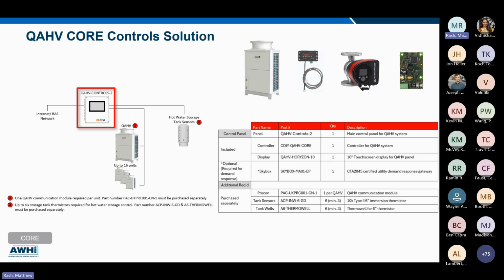That's more difficult with the core. We're doing more testing in colder climates to see if we can extend that, but in basic terms today, we're limiting that to roughly around 0 degrees F. But this does depend on several conditions: city water temperature, and what your actual set temperature is for your discharge water. So there are ways to expand that with the core. But in general, if you want up to 160 degrees on the potable side, down to minus 13 degrees, which is the minimum rating condition we have, you really have to go to the kit and the Connect.